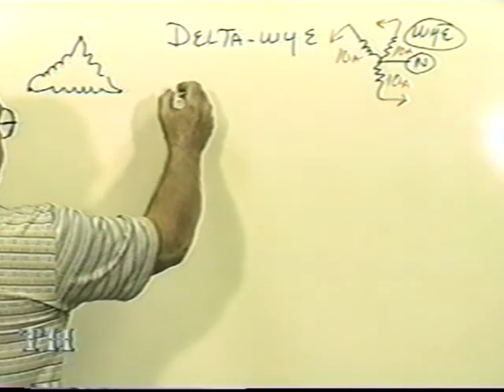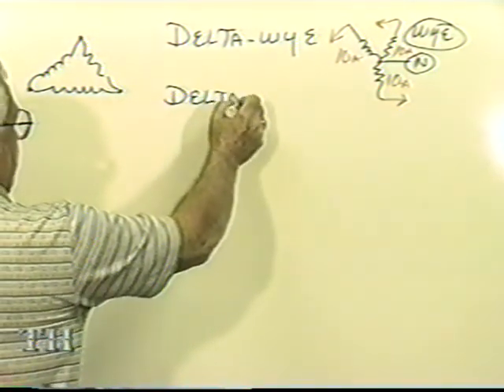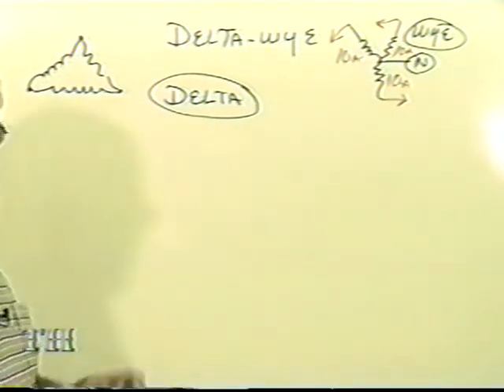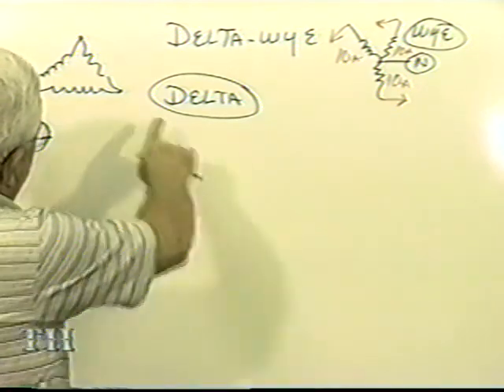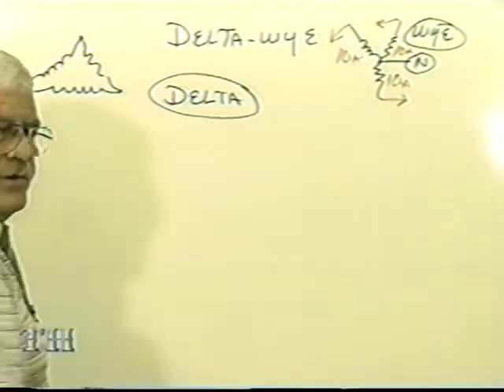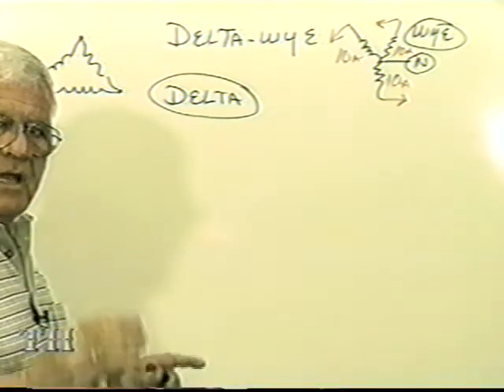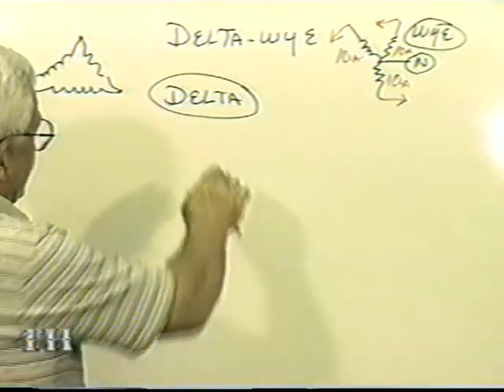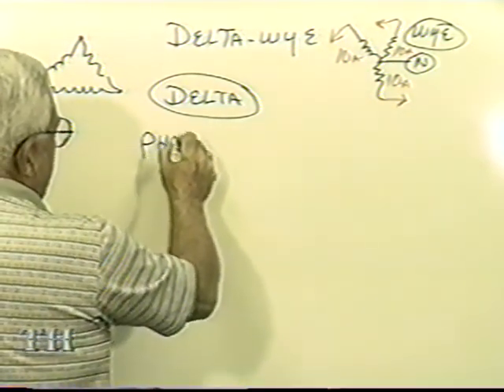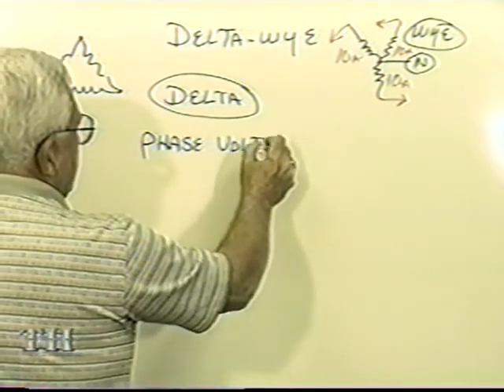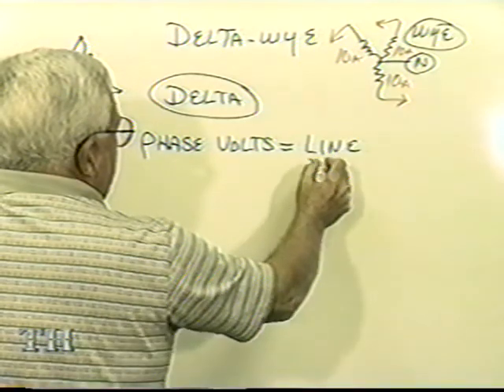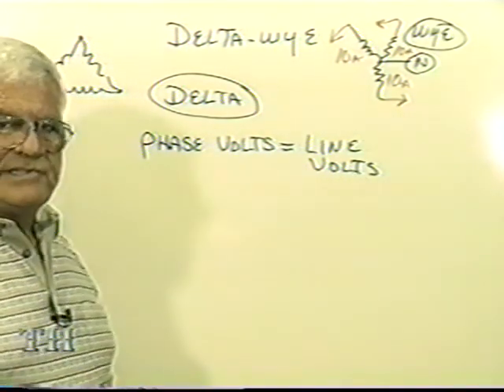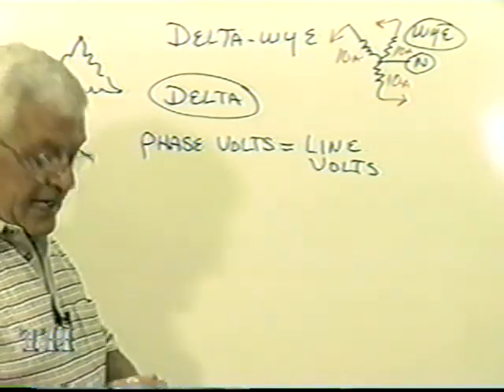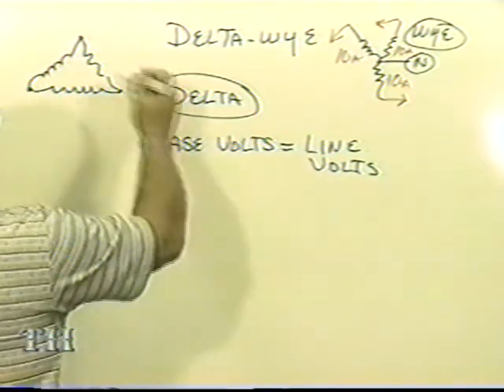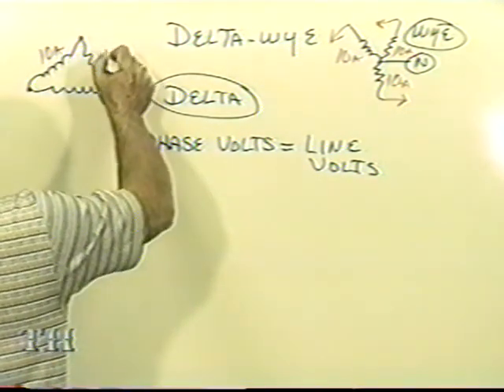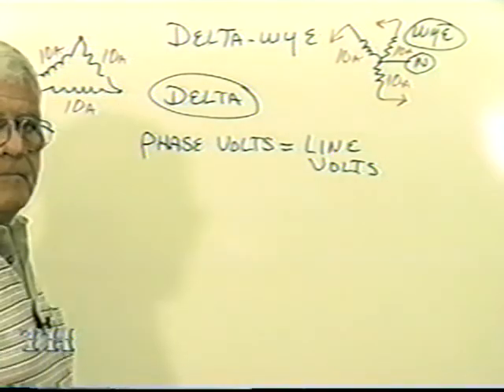Let's talk about this delta, or delta format. And you said earlier, if we put a meter right here, we would be reading 480 volts, and that we were reading line to line, and we were also reading one phase. So in a delta, watch, you can say that phase volts equal line volts. It's the same 480. That was easy. Now for the current relationship, let's say with this delta we use the same 3-phase 10 amp load like we did over here.